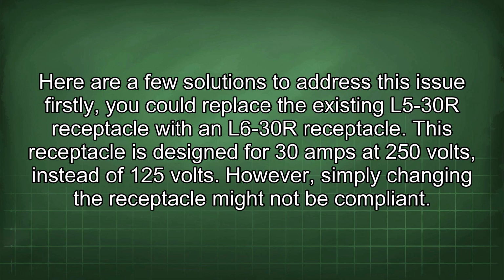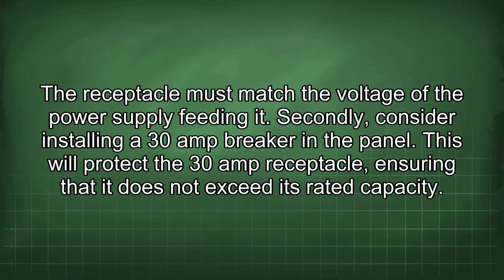Firstly, you could replace the existing L5-30R receptacle with an L6-30R receptacle. This receptacle is designed for 30 amps at 250 volts instead of 125 volts. However, simply changing the receptacle might not be compliant. The receptacle must match the voltage of the power supply feeding it.